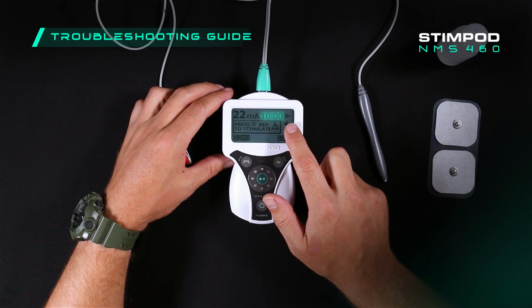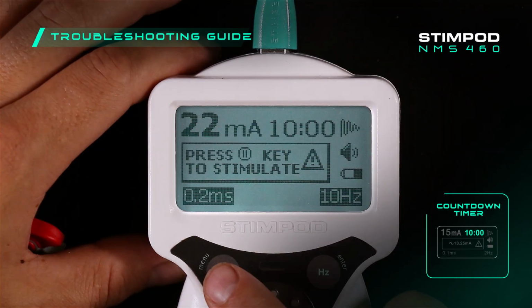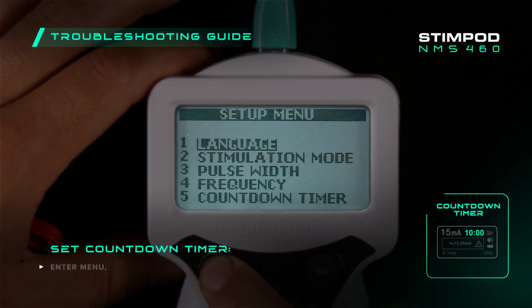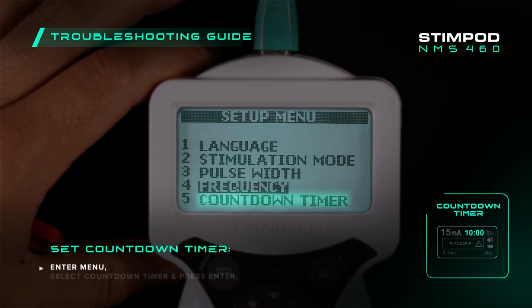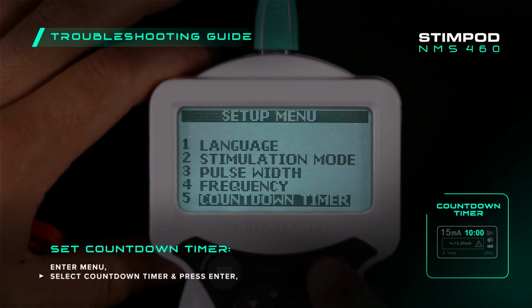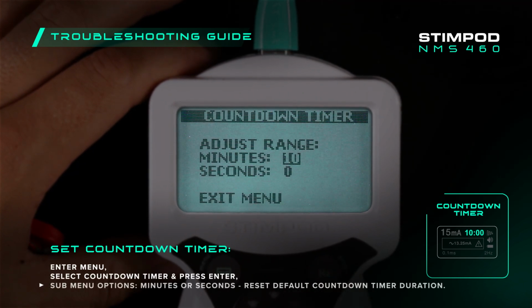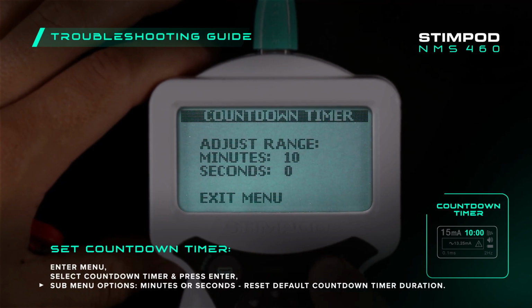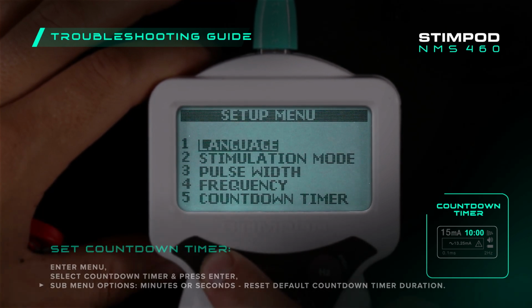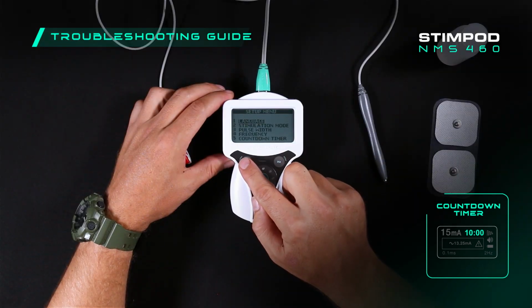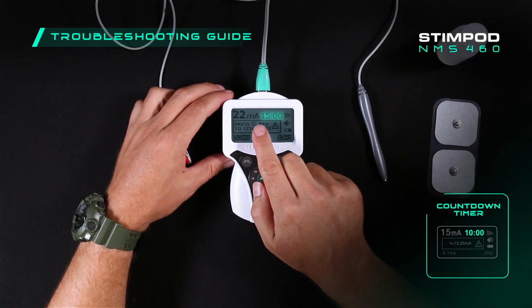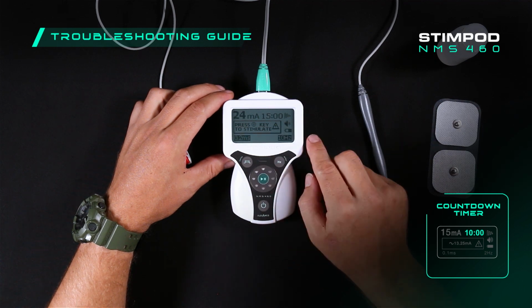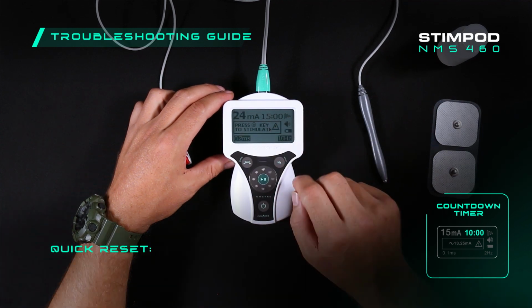You can adjust the default duration of the countdown timer in the Stimpod menu. Press and hold the menu button and follow the menu options down to option 5, Countdown Timer, and press Enter. On the countdown timer submenu, you can select either minutes or seconds. Press enter again and then roll the touch wheel to the duration you would like. Press enter to save your selection and exit the menu.